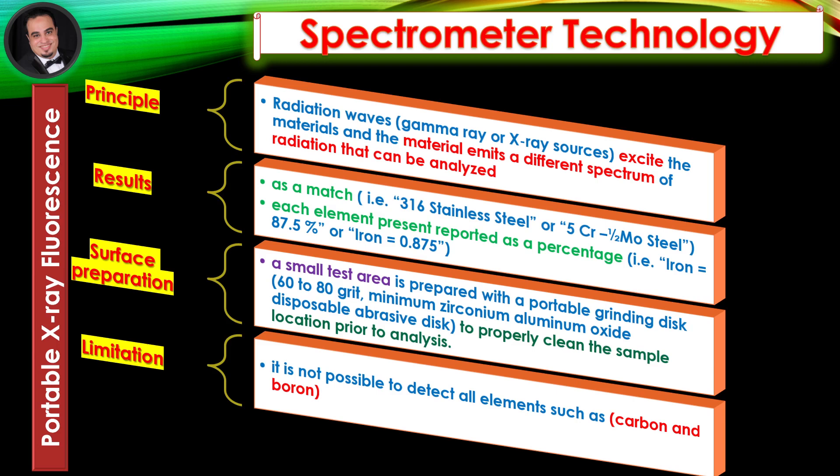Results: The results of this analysis can be reported in either of the following formats — as a match, that is 316 stainless steel or 5 chromium 1 half molybdenum steel, and/or each element present reported as a percentage, that is iron equals 87.5%, or iron equals 0.875.